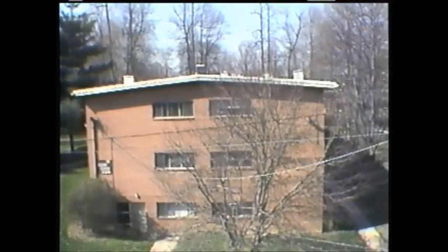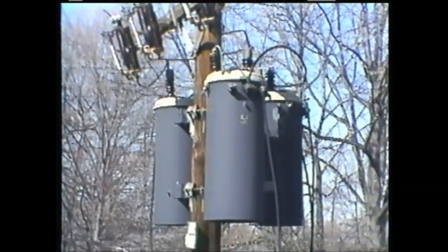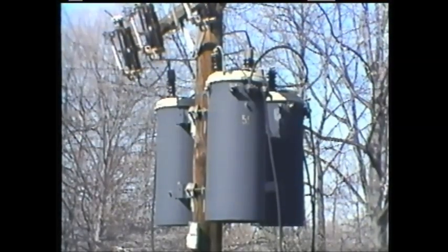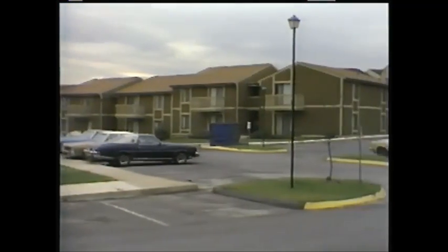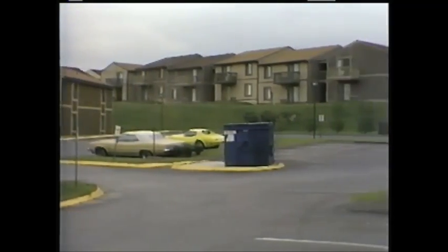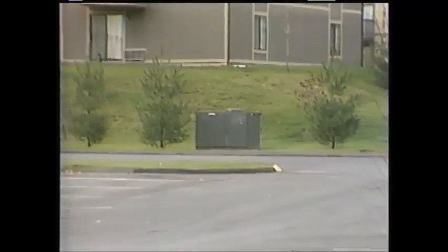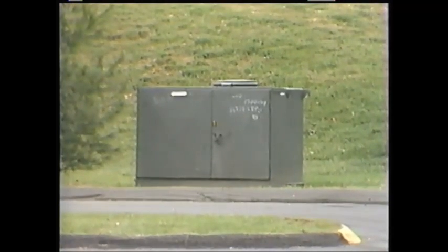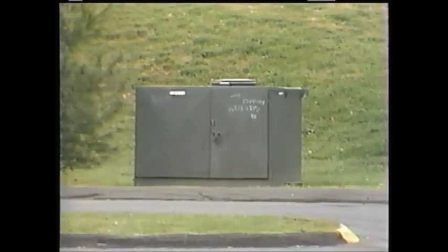In some cases, the load demand and equipment used by a consumer requires the use of a three-phase transformer. In an overhead system, three single-phase transformers can be connected together to form a three-phase transformer. Of course, not all transformers are located overhead on utility poles. In areas that have underground distribution systems, pad mounting is a common method of installing transformers. This three-phase transformer is housed in a rectangular-shaped metal cabinet that sits on a concrete pad. All connections for the transformer are concealed within the cabinet.